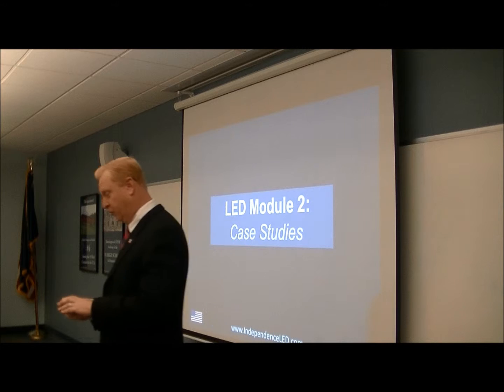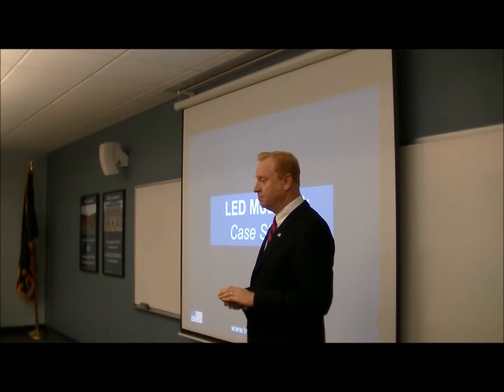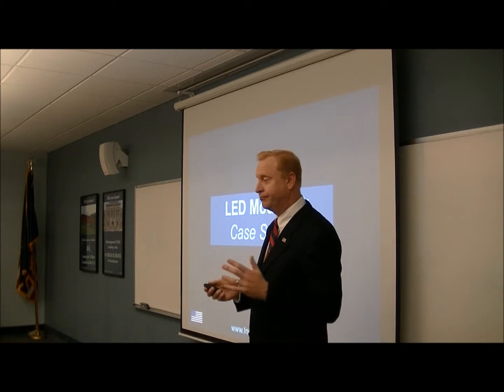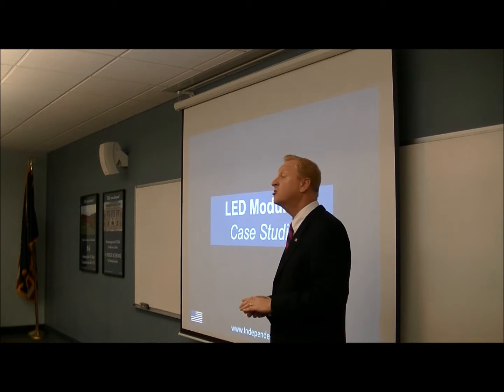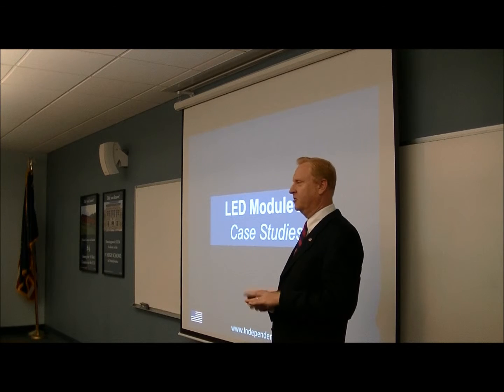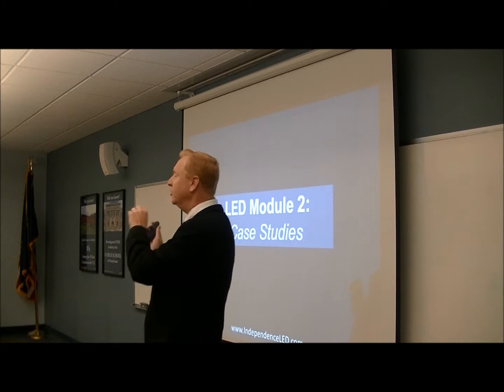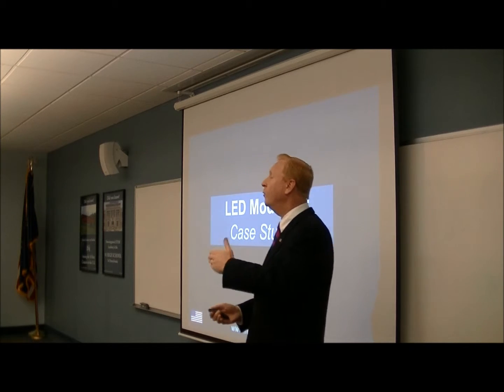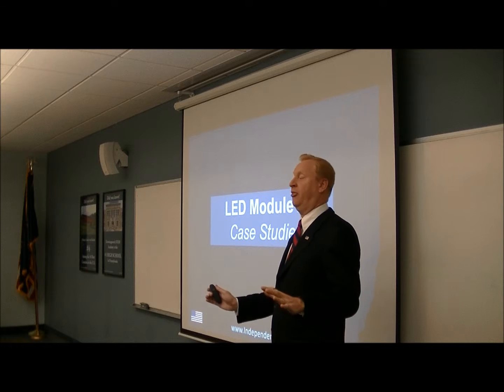And just for the sake of the group, I'll reinforce longevity. If we have 60,000 hours, and at 3,000 hours a year in an office, call it 40 to 50 hours in a week, over 52 weeks, you get into that 3,000 range. That's 20 years. Well, you'd say, Charlie, thank you for telling me your product will last 20 years. How do you know? What we do as an industry is we run 10,000 hours hot, and we look at the degradation level to see how many percentage points we've lost in output. And then we expand that over the life to get to what is called L70 death.